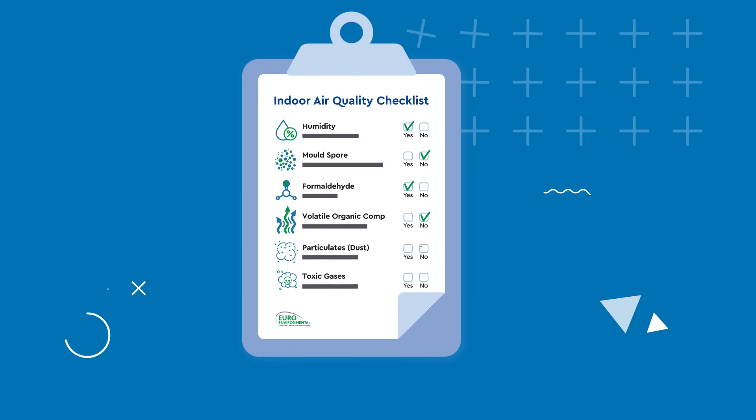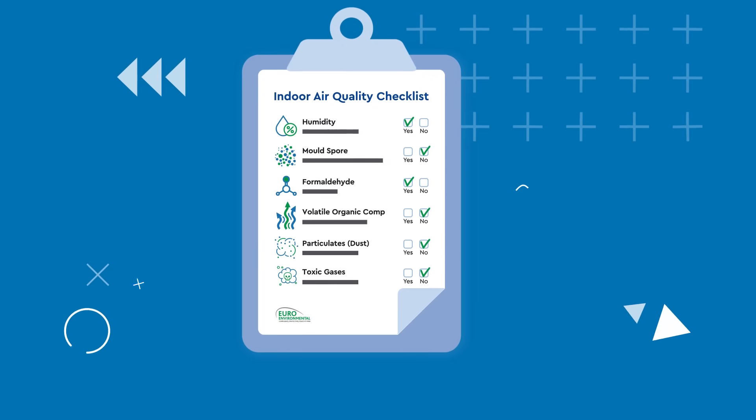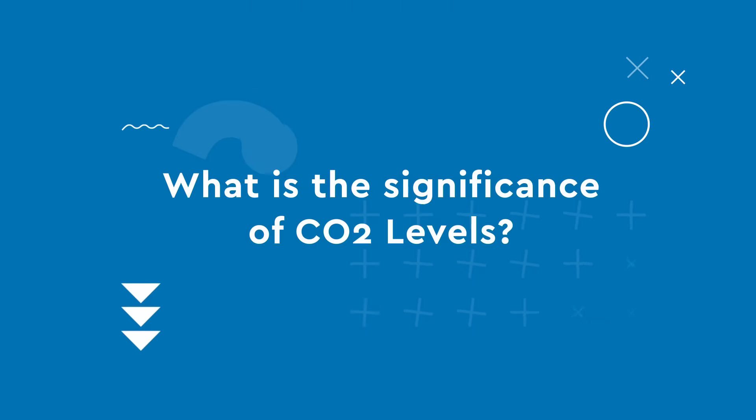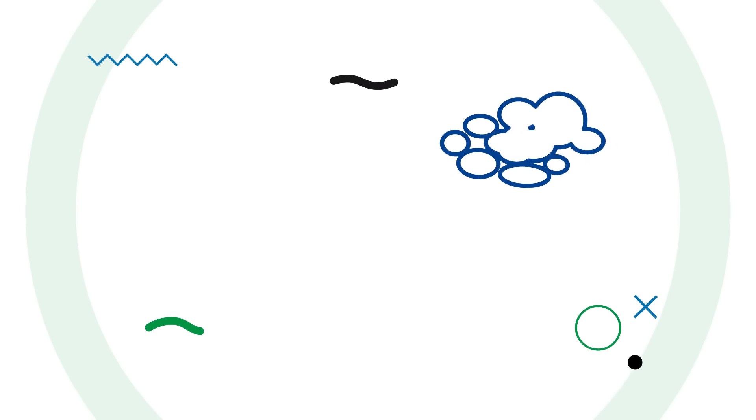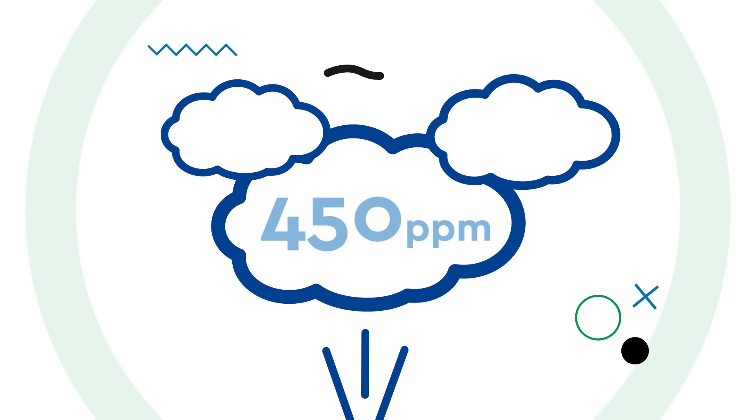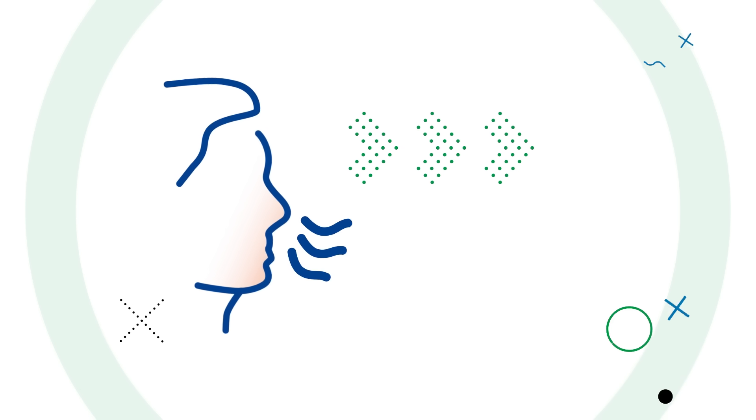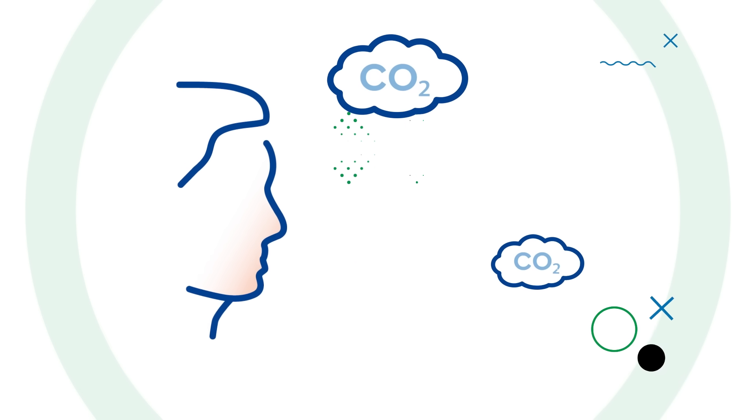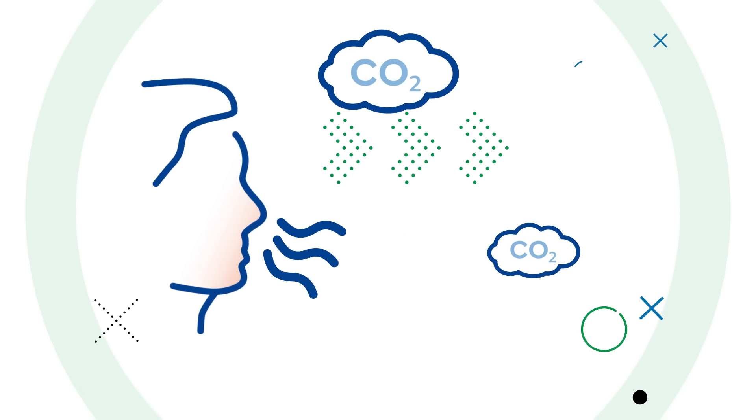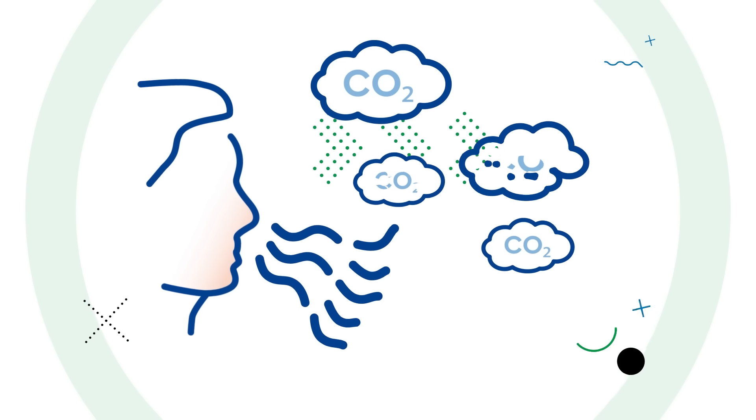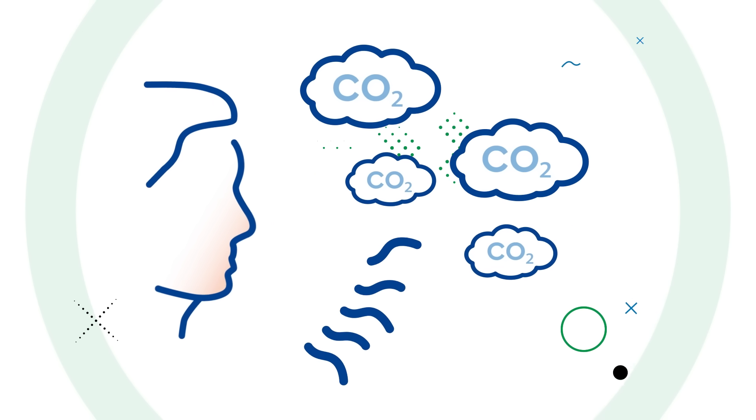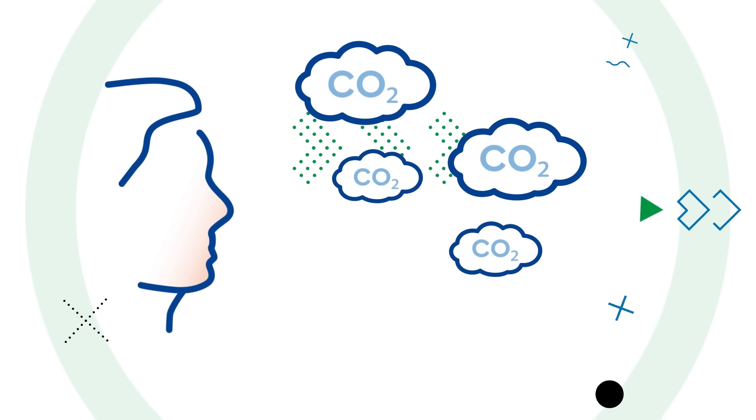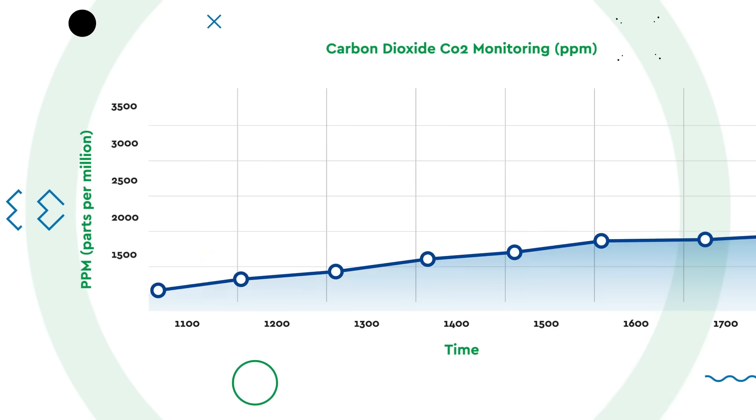What is the significance of CO2 levels? Carbon dioxide levels in fresh air are 450 parts per million. As we breathe, we generate excess carbon dioxide, which increases the overall concentration of this gas in the indoor environment. A poorly ventilated workplace with very little fresh air can easily see levels over 2,000 parts per million as the working day progresses.